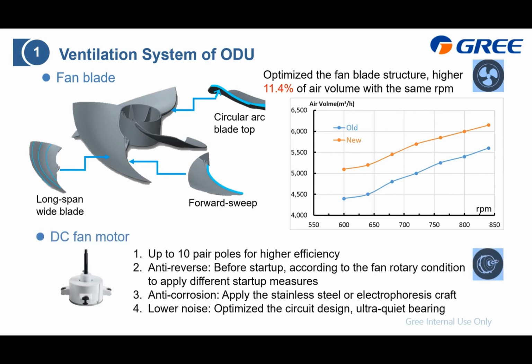As for the fan motor, first is the anti-reverse. That means when the U-Match is going to start up, first we will judge how the outdoor fan motor operates: clockwise, stop, anti-clockwise, and according to this one, we will have different measures to ensure it can start up successfully. Anti-corrosion, that means the whole body or even the shaft, we apply stainless steel or electrophoresis craft. Low noise, that means inside there is a built-in PCB to drive the fan motor, and for that we also optimize the circuit design to ensure when the fan motor operates it will not have electronic noise.